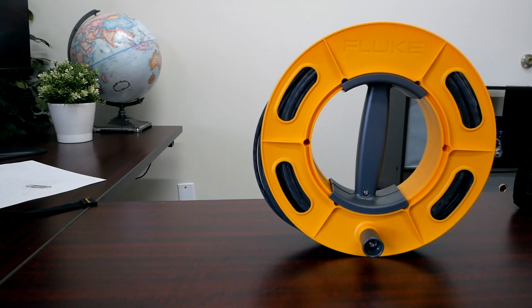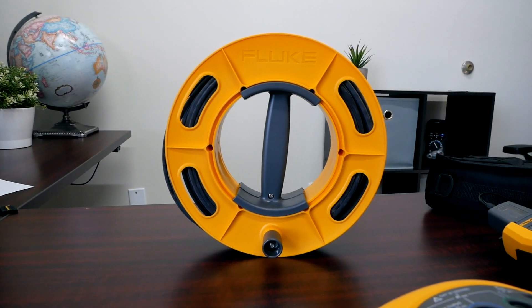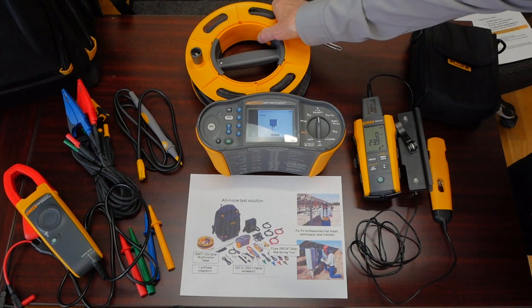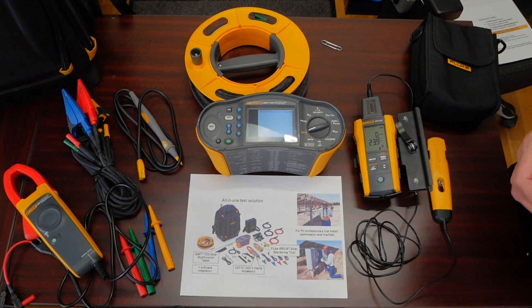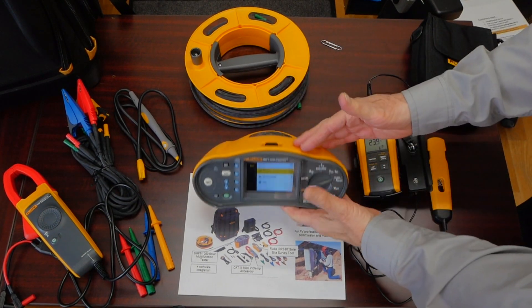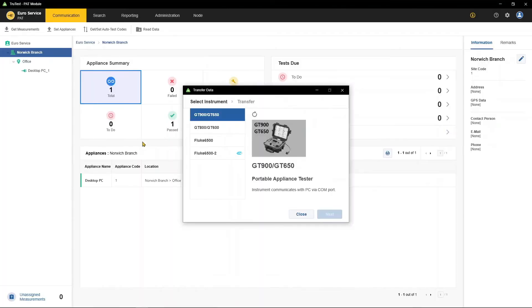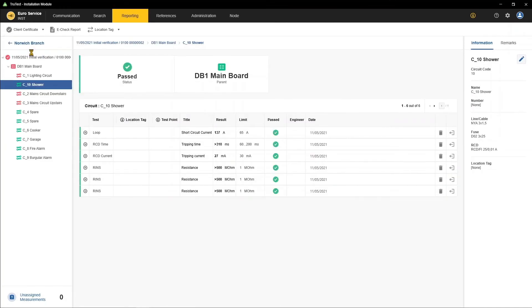A 50 meter reel of ground wire connections lets me test my grounding when doing point-to-point connectivity on my ground system, making sure everything is bonded correctly. All this wraps up to the ability of taking all the data and downloading it through the memory on our optical interface on the top to the TruTest software, which comes as a complete suite and provides reporting so we can go paperless in the field.